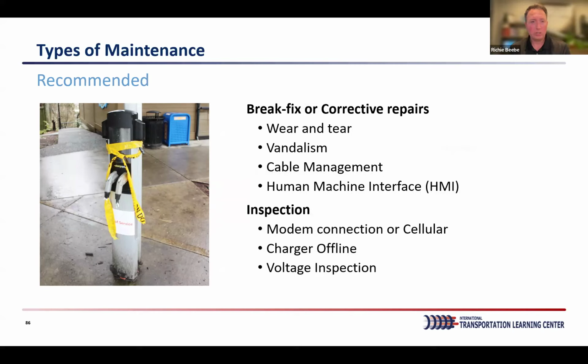And then we do see a lot of maintenance dispatches that would be because of a charger being offline, the cellular connection isn't working, or there was an issue with the electrical infrastructure, maybe a power outage, or a main switchgear loses a leg. So verifying that the voltage is correct to what the manufacturer requires. And again, this is all recommended type of maintenance, recommended type of commissioning and preventative maintenance.